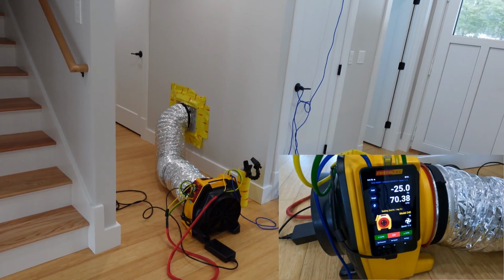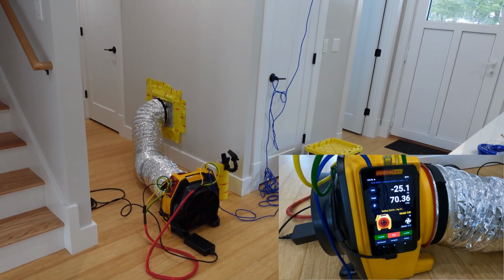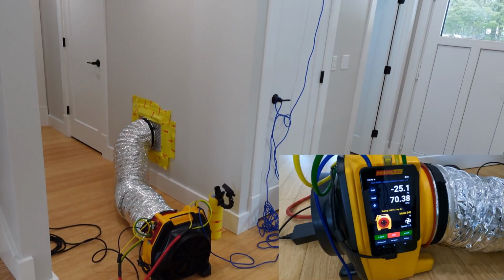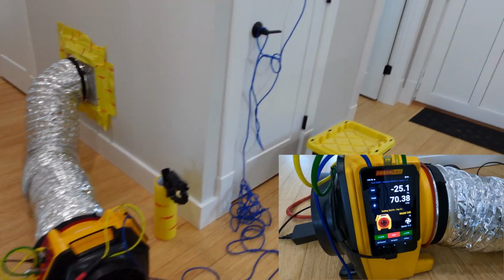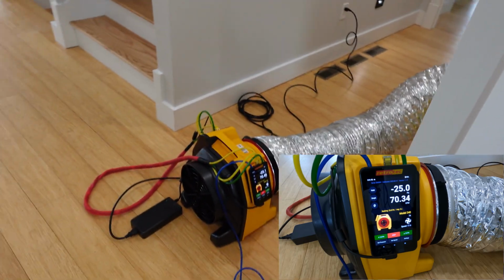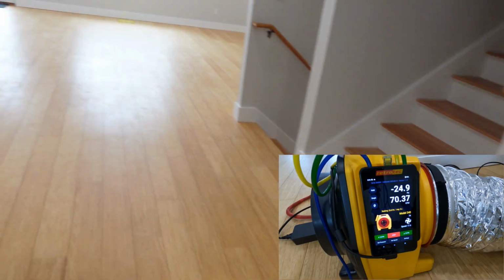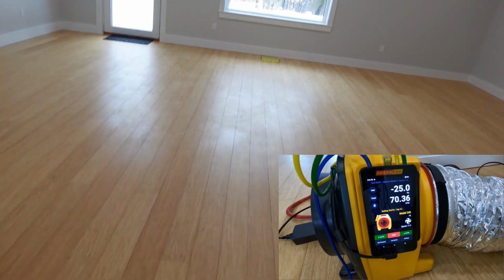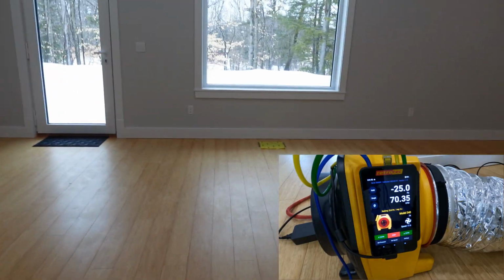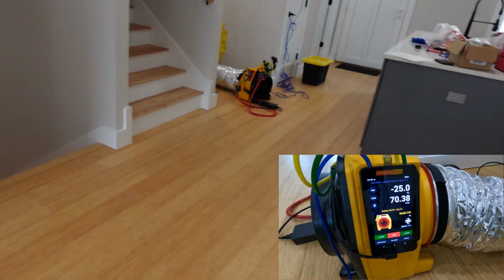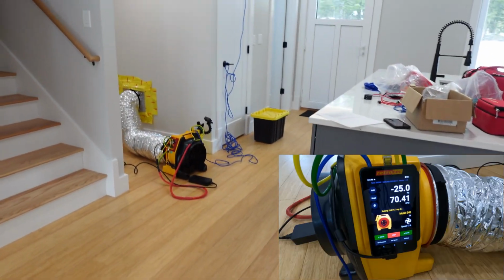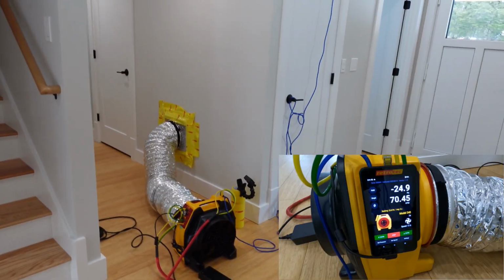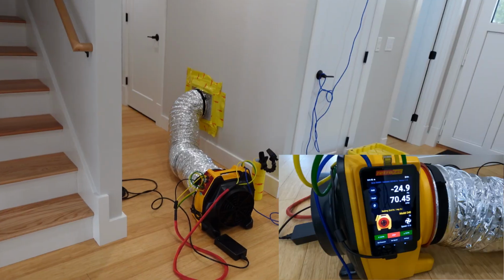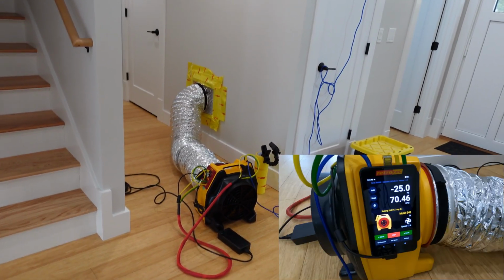You're allowed 4 CFM per 100 square feet. So 26 times 4 is 104. I'm allowed 104 CFM, and I'm at 70. Now New Hampshire's code is 8 CFM per 100 square feet, so I'm allowed 208 CFM, but I'm only at 70. So the system's pretty tight. I'm happy with how it's performed, and I'm happy with the flow rates.